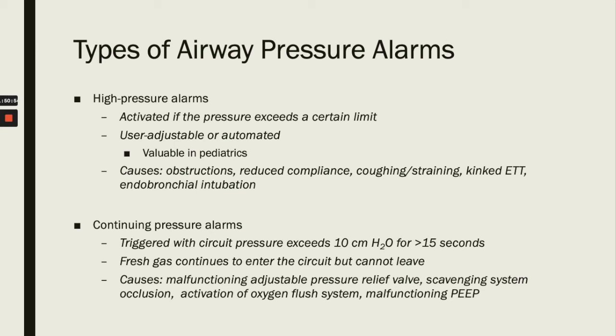Essentially, with the continuing pressure alarm, the rate of rise of the circuit pressure depends on the fresh gas flow rate.